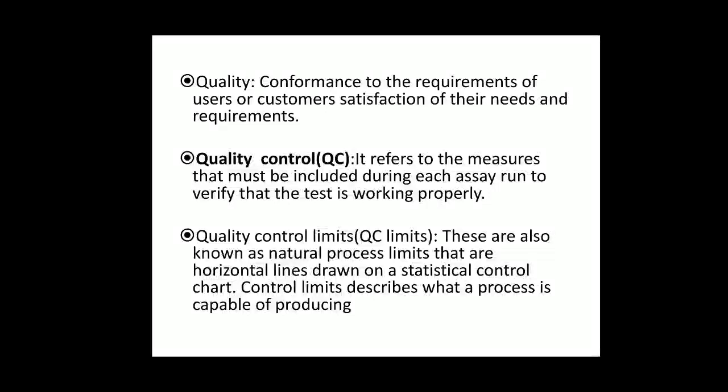If it is exceeding the limit, then we have to calibrate, rerun the QC, then rerun the test. That means if it is outside the limit, exceeding the limit, we should not dispatch the report.